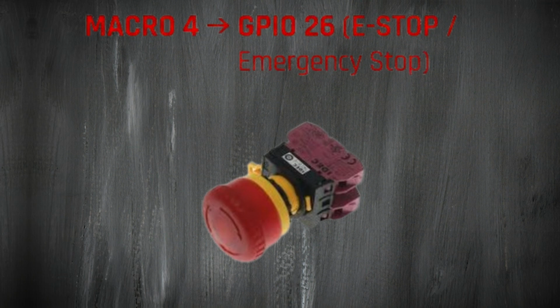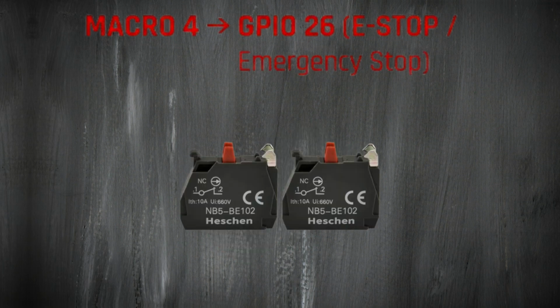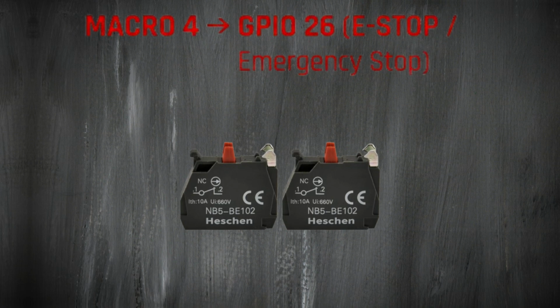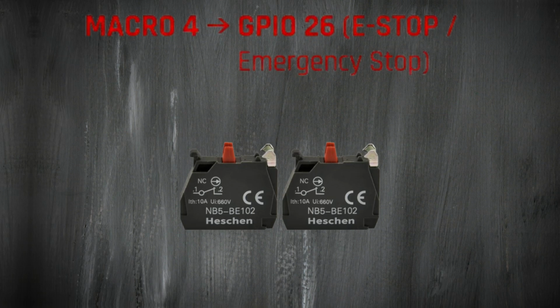However, when it comes to the stop, we have to pay special attention to how it's wired. To achieve maximum safety, our mushroom button utilizes two completely separate, isolated normally closed contact blocks inside it. Here is how the dual protection system works.